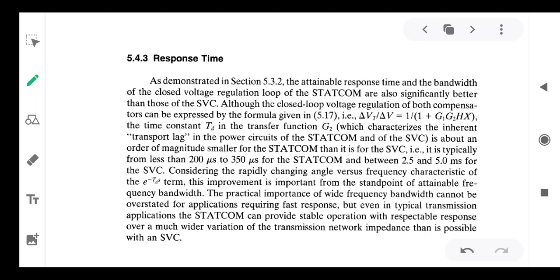Coming to the operating time and response of the SVC and STATCOM. SVC is comprised of TCR and TSC. The TCR operating time is 2.7 milliseconds and the TSC operating time is 5.5 milliseconds, whereas the STATCOM converter based controller operating time is very low, that is 0.5 milliseconds, and hence coming to the dynamic performance, the STATCOM is much more superior to that of the SVC. Generally STATCOM is the latest device in FACTS devices, whereas SVC is the early device. So therefore you can easily understand that STATCOM is much more superior than that of the SVC.